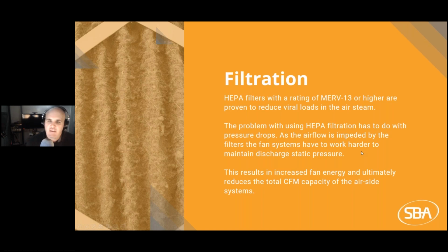And we all know in the plan and spec environment how notoriously undersized systems can be. Systems will get undersized, they will barely be able to handle design days anyways, and now we are introducing a pressure drop that they were not sized to deal with, and we're going to see units that on design days cannot maintain the environment, and on non-design days are operating, at least on the fan side, at design day loads. So this is going to increase fan energy, and ultimately it's going to reduce the total CFM capacity of airside systems, which actually causes some challenges for the ASHRAE recommendations.